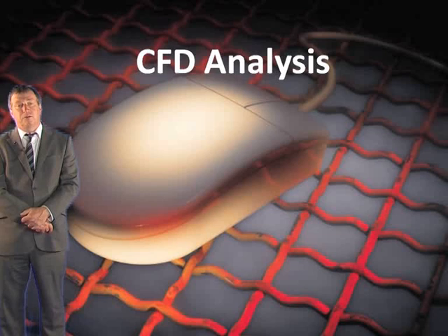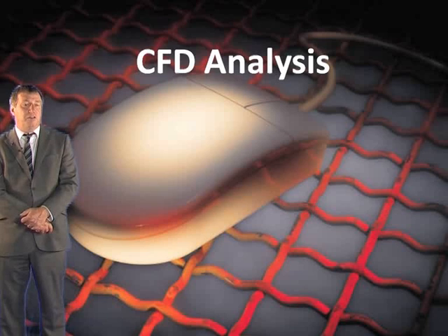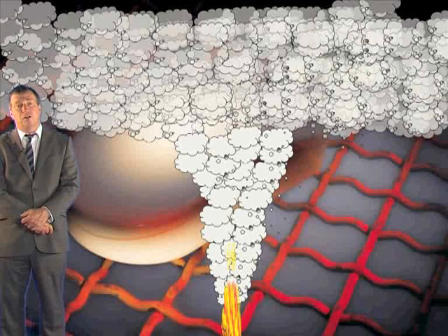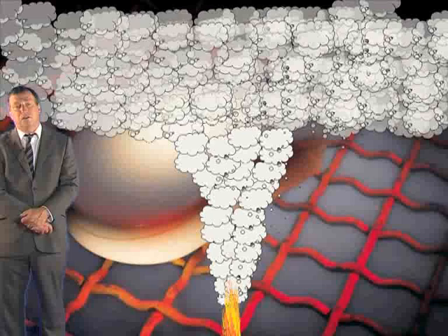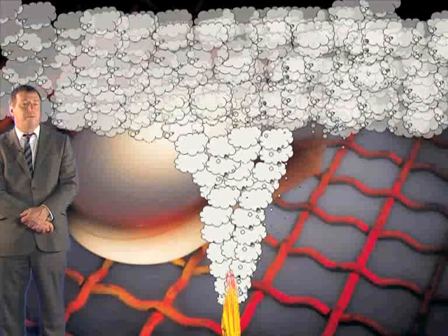Computational fluid dynamics, or CFD, can be used to assess if smoke will remain at ceiling level, but there have been a number of cases recently where fire engineers have made erroneous assumptions when carrying out this analysis. For example, errors in the assumed rate at which heat is lost to the ceiling or walls, or inappropriate cell sizes have led to incorrect conclusions about the behaviour of the smoke. Such assumptions should either be very accurate or should err on the side of safety. Also, provisions will be required within the CFD model to ensure that an accurate assessment can be made of the behaviour of the smoke and of the outside air at all open ventilators.